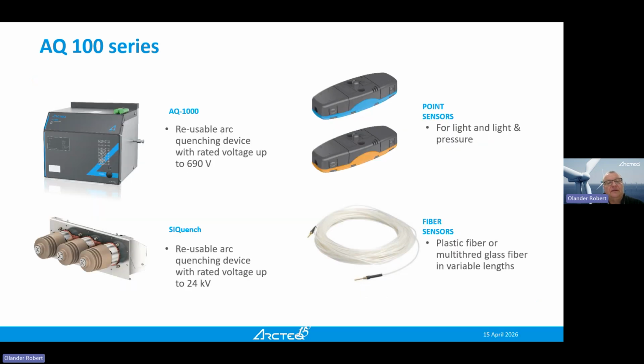And then we have the quenching devices here, which make it much faster, taking the arcing time down to 4 milliseconds. This is because even if you have a short circuit current of 50 kiloamperes, even the 70-80 milliseconds delay of the breaker is too much. It will destroy the switchgear quite thoroughly already by then. And then you need to install also a quenching device. So basically what a quenching device does is that inside of the quencher, it will create an internal short circuit.